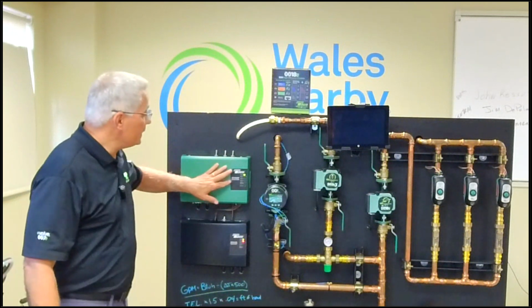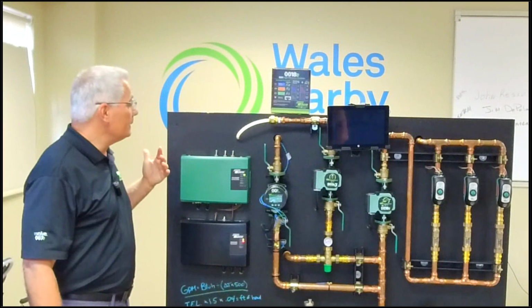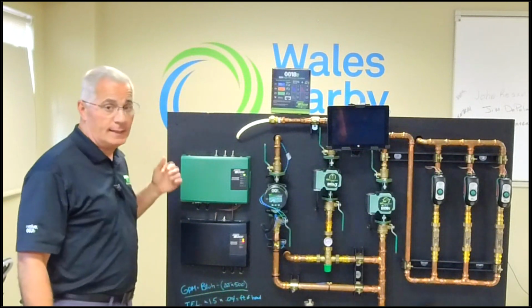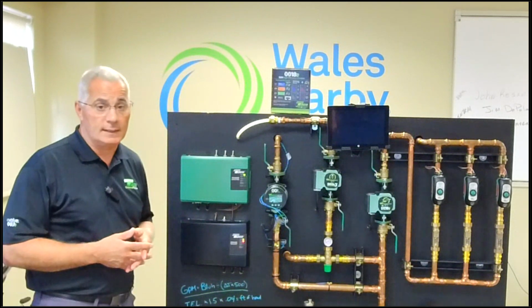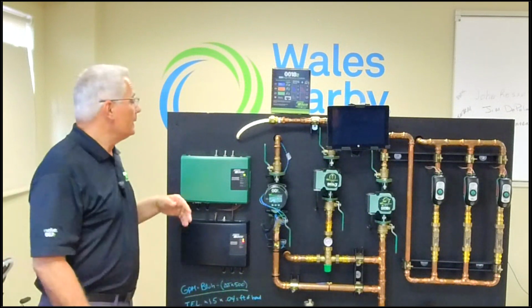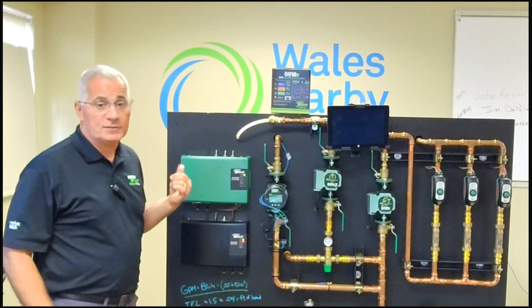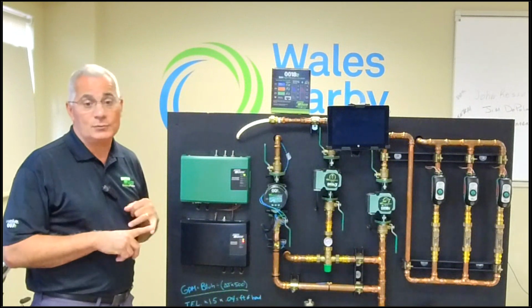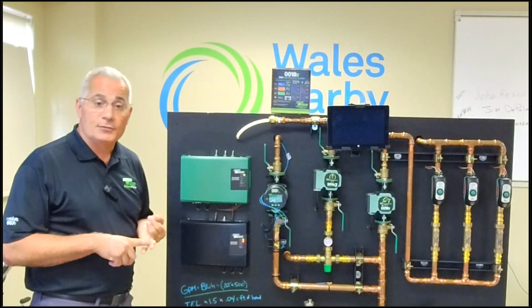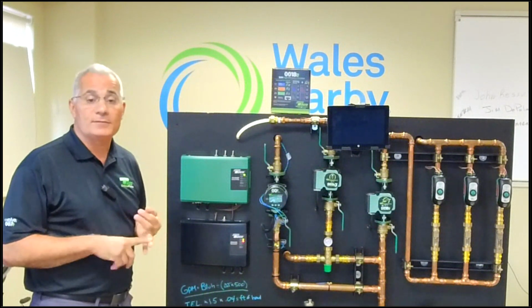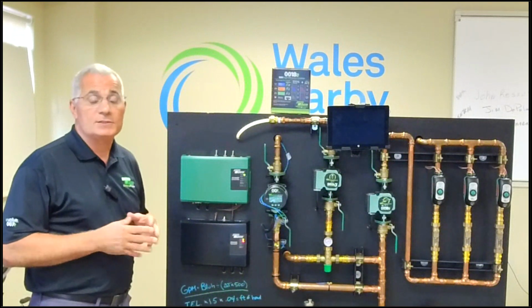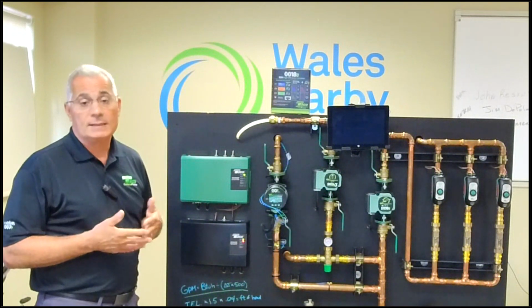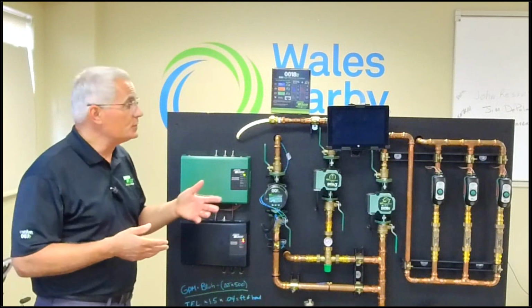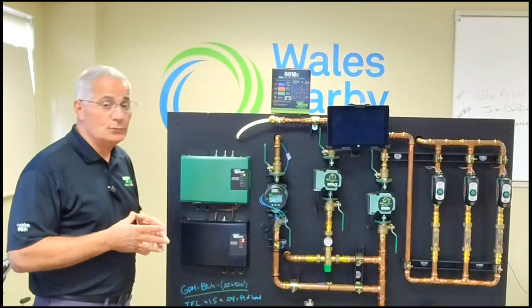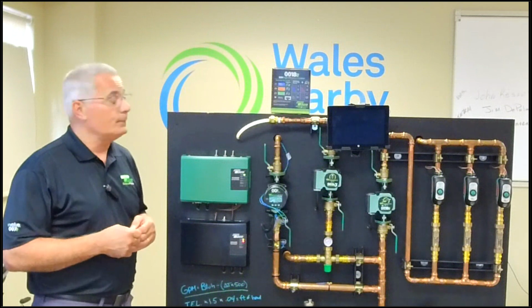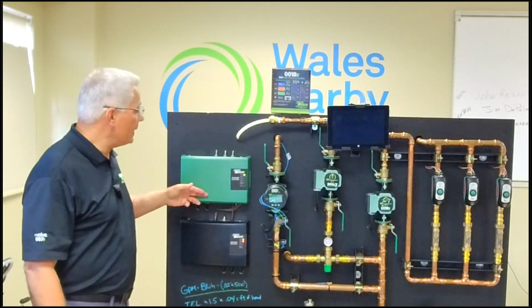I really like these panels for a lot of reasons. Number one, as long as I have power brought to the panel, I really don't need an electrician to hook anything up. And I can run anybody's zone valves on here, whether they're 2-wire actuators, the 3-terminal, that would be the TACO 570 series, or anybody's standard 4-wire zone valves. It could be Honeywell, it could be Erie, but here we're using our TACO Zone Sentry. And I have them wired here at the bottom.